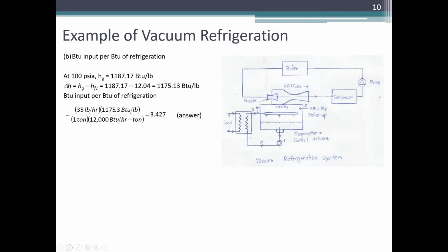Now, BTU input per BTU of refrigeration. So, meron tayong, di ba? 1 ton. So, at 100 PSI, HG is 1187.17. So, delta H is equal to HG minus HF1 is equal to 1187.17 minus 12.04 is 1175.13 BTU per pound. This is the boiler load. Di ba? Lumabas siya is saturated at 100 PSI. Pumasok siya ng HF1.